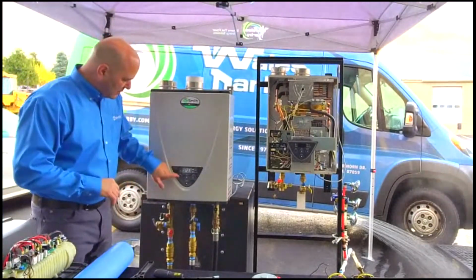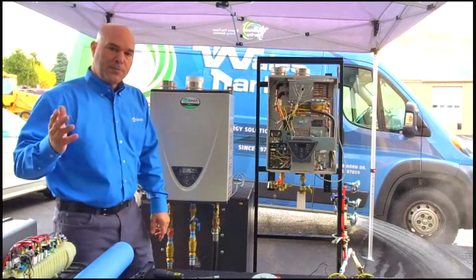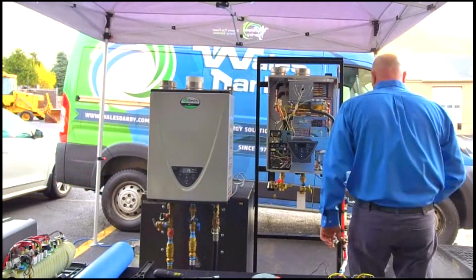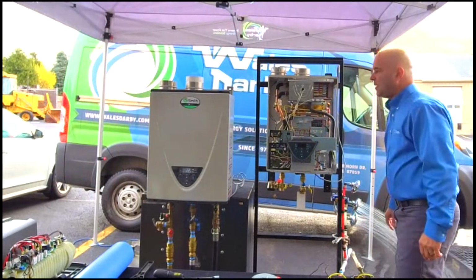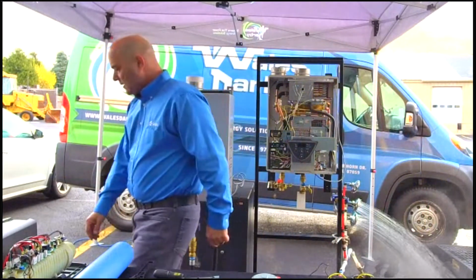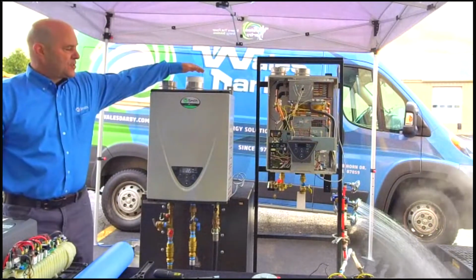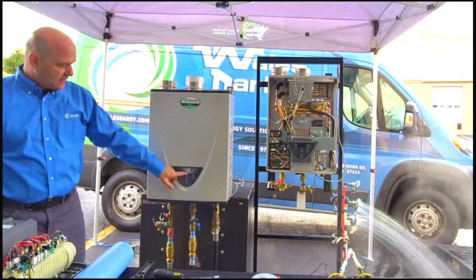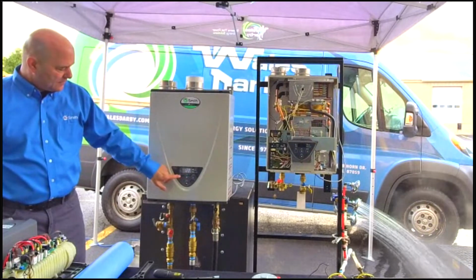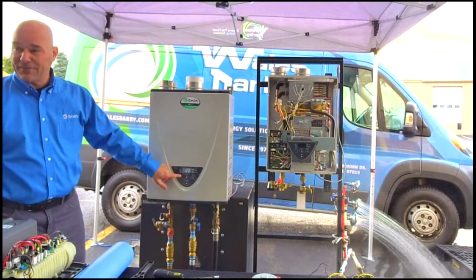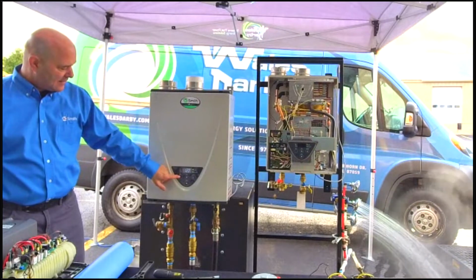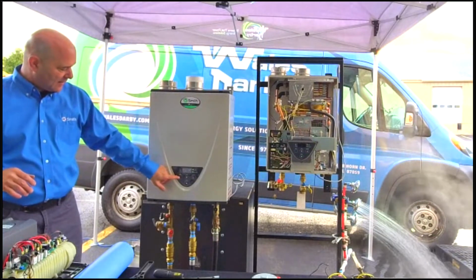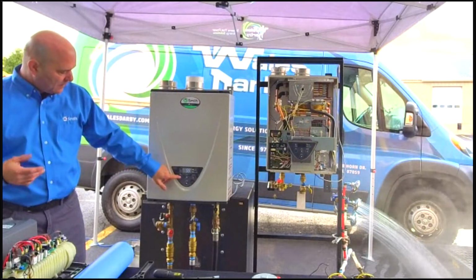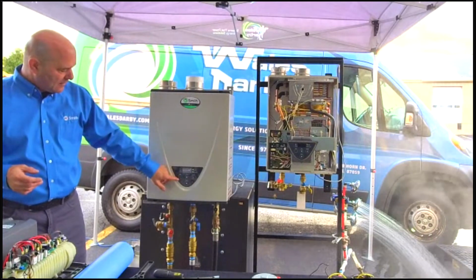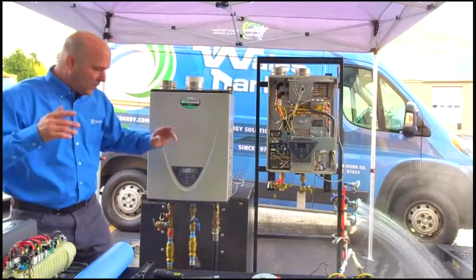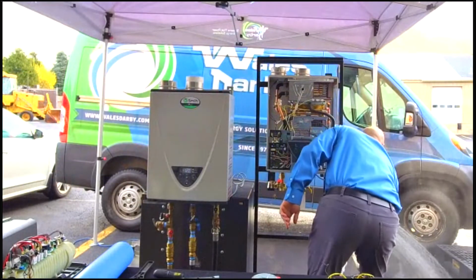Okay, so let's go to the next step. I am at 1.4 gallons of flow. I can open up another shower, and it just ramped. It recognized it. Our flow rate is still going. We are on like 75 feet of hose, guys and ladies. So we might be a little pressed to get real high flow rates out of it. But we have 55-degree water coming in, and we are hitting our 120 degree going out.